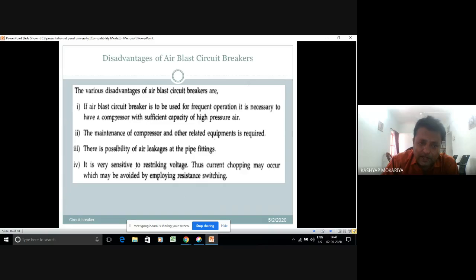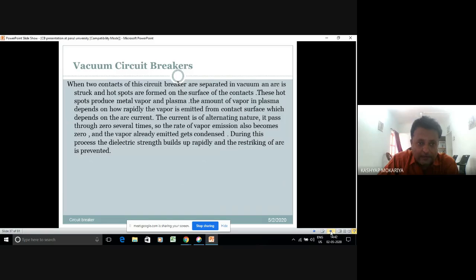Disadvantages: if the air blast circuit breaker is to be used for frequent operation, it is necessary to have a compressor with sufficient capacity. You must have a compressor. The maintenance of the compressor and other related equipment is required from time to time. Leakages of air in this system have to be checked. The pipe fitting arrangement has to be checked. It is very sensitive to the restriking voltage, thus current chopping may occur, which we already discussed. And the resistance switching unit, as shown in the slides, was fitted to deal with this phenomenon.